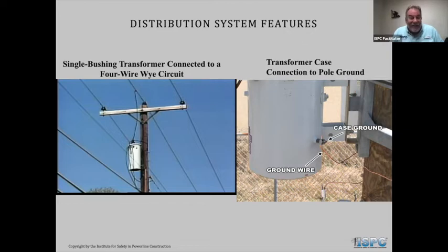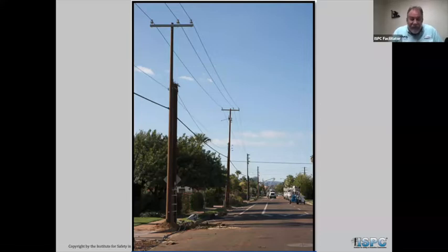So we've had instances in the past where that ground wire came off, it energized the transformer or the bolts that are going through the pole. It actually burned a hole in the pole, and the transformer fell off of the pole as the bolts heated up and burnt the pole in two. So there's a lot more hazards out there than a lot of our guys think about.